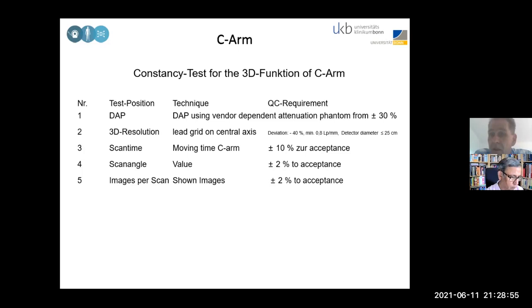Then you need the scan time of the C-arm. So you have to check whether the angle per time changes in the manner it changed before. Then the scan angles, are they right? So if you would like to have a 45 degree angle, you have to check its geometry. And of course, now we come to a very important part, which I find usually a little bit underestimated, which is the images per scan. So if I do a scan with a C-arm, how many images do I actually do? Because they are given in the protocol.